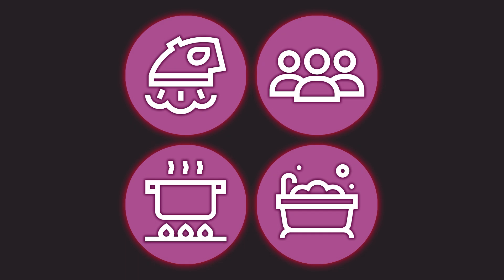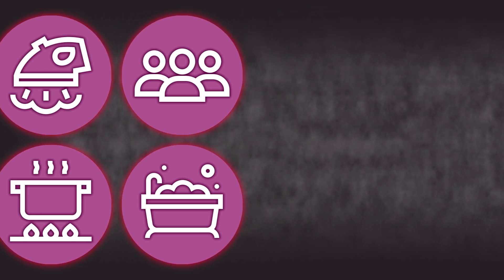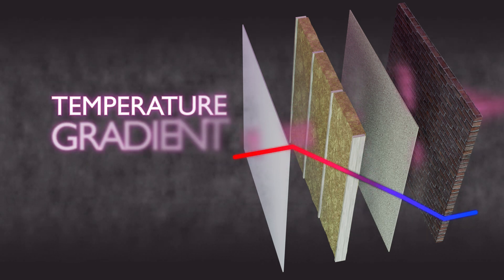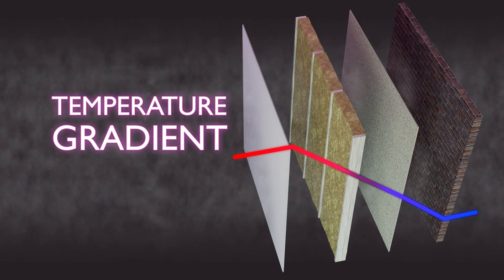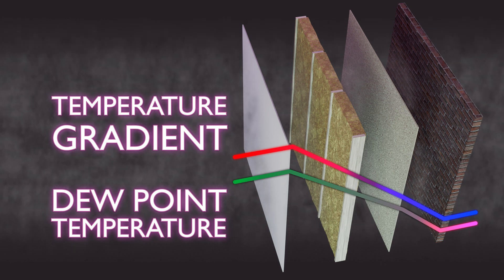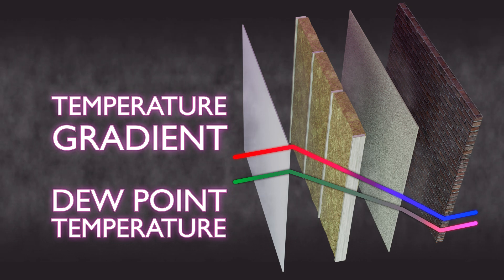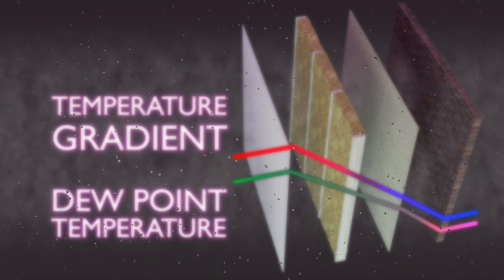So what is condensation and what causes it? Most everyday human activities such as cooking, cleaning and even just breathing generate moisture vapour, and this, combined with warmer indoor environmental conditions, causes what is known as vapour pressure, pushing the moisture outwards into the building fabric. As we move through the fabric of the building, the temperature drops until it reaches the outside temperature. The warmer the air is, the more water vapour it can carry. So as this temperature drops, at a certain point the air will become saturated and dump this vapour out as liquid water — this is called the dew point. This is the same effect that causes bathroom mirrors to steam up or water droplets to form on a cold drink can. If it occurs within the building fabric, it can cause damage or mould growth.